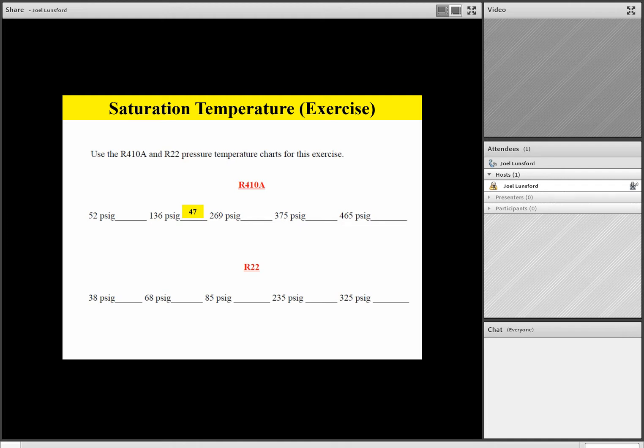So our next one, 410A, is 269 PSIG. Please convert that to temperature. Good, it should be 89 degrees. The next one is 375 PSIG off the 410A chart. And we see that's 112 degrees Fahrenheit. The final example for 410A in this exercise is 465 pounds of pressure, PSIG, equates to what temperature? Okay, good, 128 degrees.